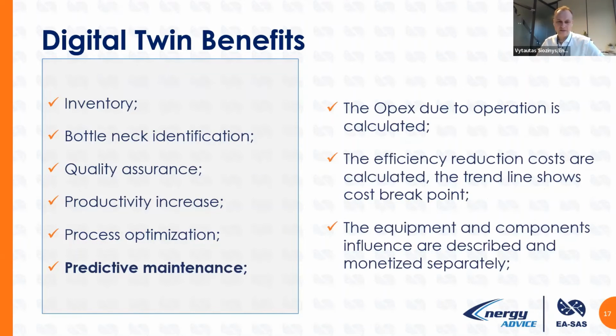And predictive maintenance: we always have OPEX due to operation, and we calculate this OPEX, and efficiency reduction costs are calculated. Trend lines show the cost breakpoint. So what does cost breakpoint mean? It means that you would understand accumulated losses in euros, and here would be your target to do maintenance, because up to this moment losses you could tolerate, because in euros they were smaller, but after some breakpoint losses in euros would be intolerable, and you should do some maintenance. Equipment and component influence are described and monetized separately, so we analyze separate equipment parts to predict the behavior of each component.